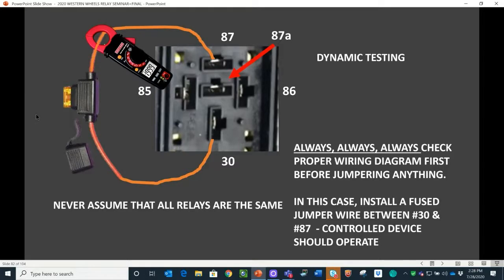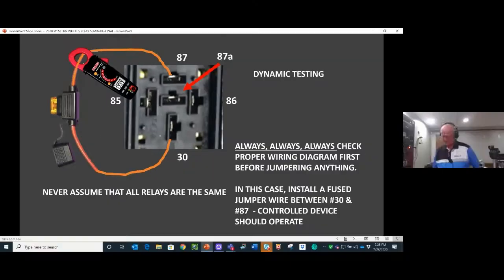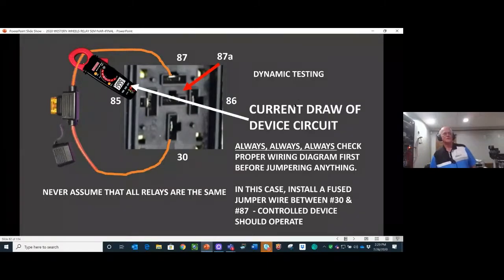In this case, I have connected an inductive ammeter, or I could put an ammeter in series with the jumper, it doesn't matter. And I'm now reading current flow. What does that current flow mean? What am I measuring? Well, if this relay was controlling a fuel pump, am I measuring the current flow of the fuel pump? Yes or no? And the answer is no. It is the current draw of the device circuit, not the device.